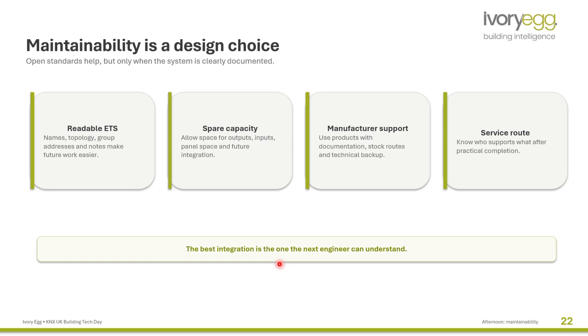You should have spare capacity when you do the design, for outputs, inputs, and so on. Use products from manufacturers that are responsible for their products. You do not install KNX or BMS products for just 2 or 10 years; we are installing for at least more than 10 years, maybe for the whole building life. So choose reliable manufacturers, not ones that don't take care of their products. The best integration is the one the next engineer can understand.